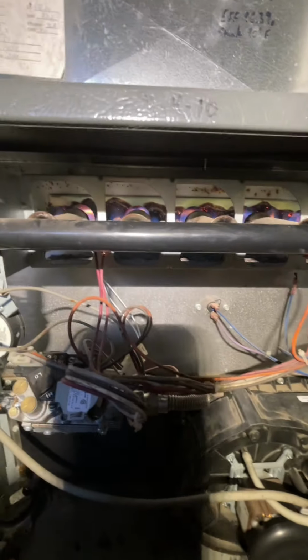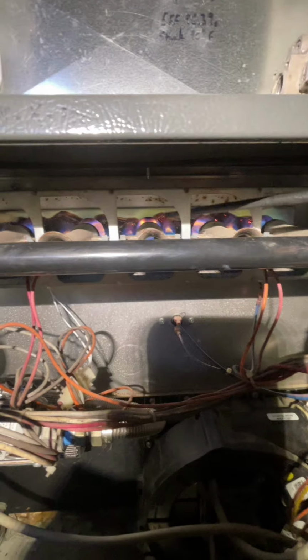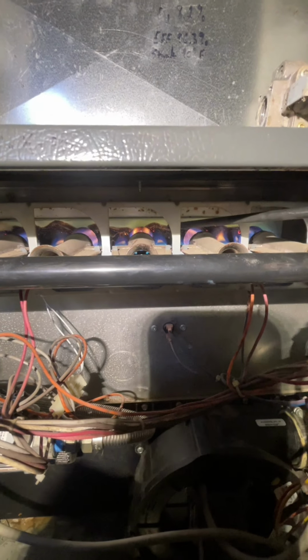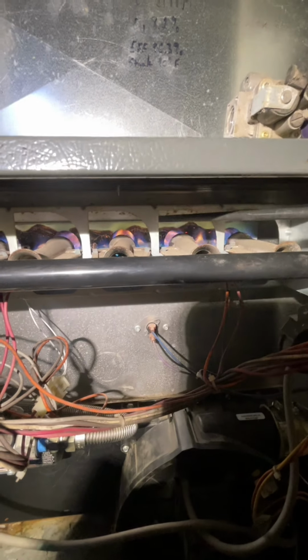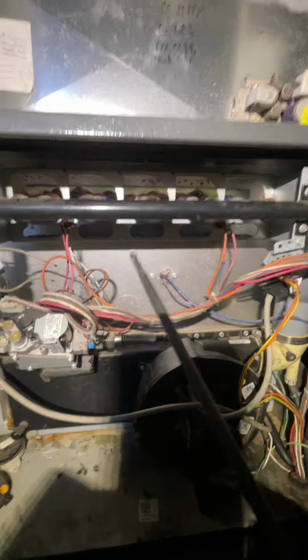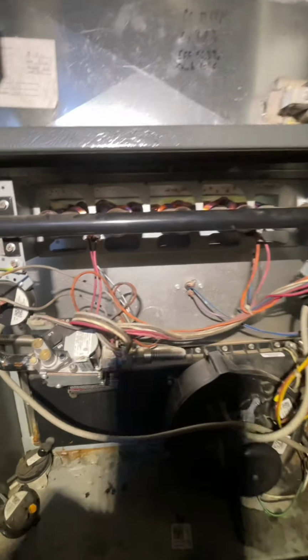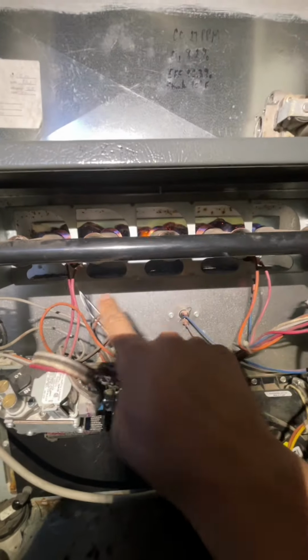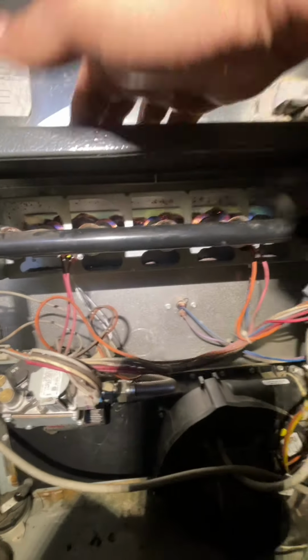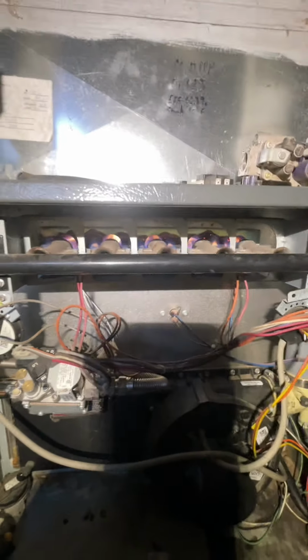The secondary heat exchanger is plugged up. When you're looking at this, you can see the flame is not totally going down the hole. Where I've got that bit there, you can see all that rust, and there's also this greenish yellow silhouette around there. This is indicative of the motor not being able to pull enough pressure, so all the flame sort of stays right here in the burn chamber. It's real hot up here.